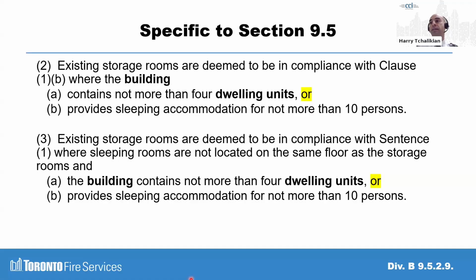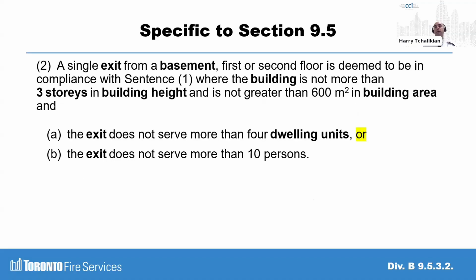And A, the building contains not more than 4 dwelling units, or provides sleeping accommodations for not more than 10 persons. Subtle change. The highlighted ors used to be ands, which means you used to have to meet both of these conditions for that to apply. Now you just meet one of those conditions. Furthermore, very significant, this is where it actually has already even come up with inspectors.